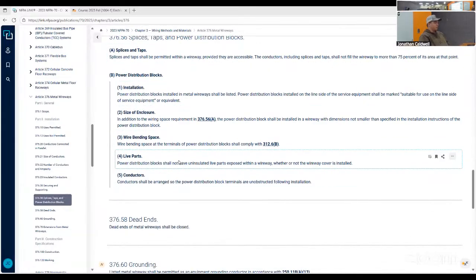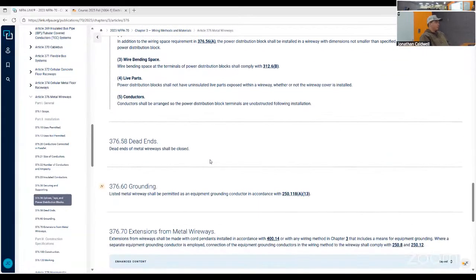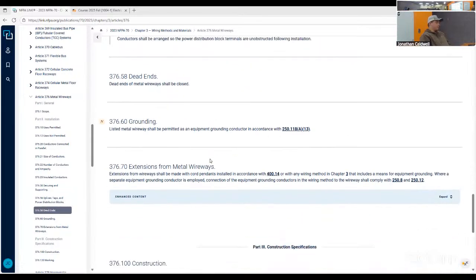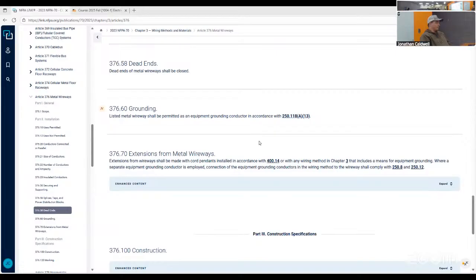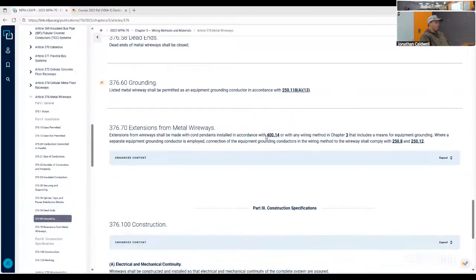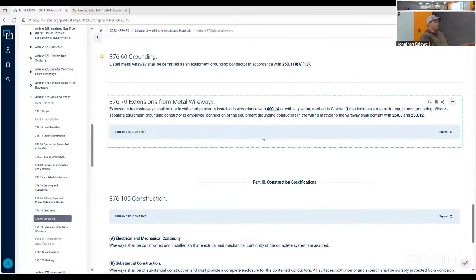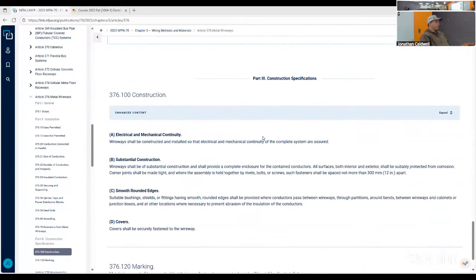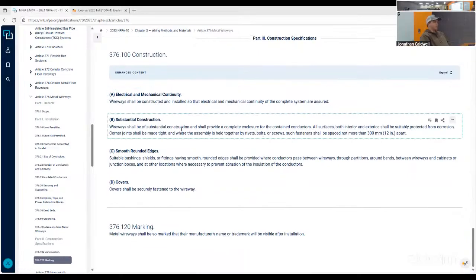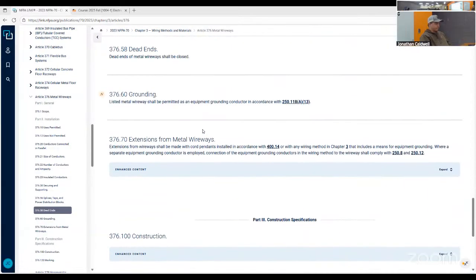Power distribution blocks, live parts, conductors. You must use dead ends for your wireway. You can't just leave it open. And manufacturers do make metal wireway extensions. They make boxes for them. They can just go right into things like that, or even really hard 90s. And then it just talks about construction and marking.